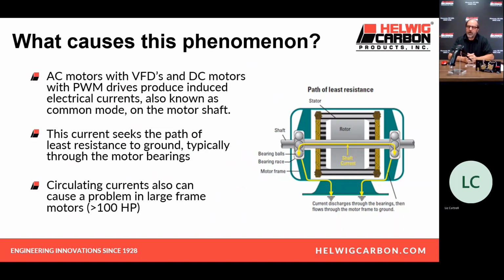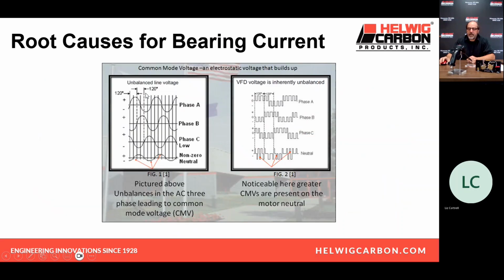The other thing that's going to cause the problem in the motor is circulating currents. Circulating currents are typically only things you'll see above 100 horsepower before they begin to damage your motor and bearing. If you're not seeing electrical discharge through common mode, through PWM sources, we also should address circulating currents within the motor. That's a separate issue, and we can address that.